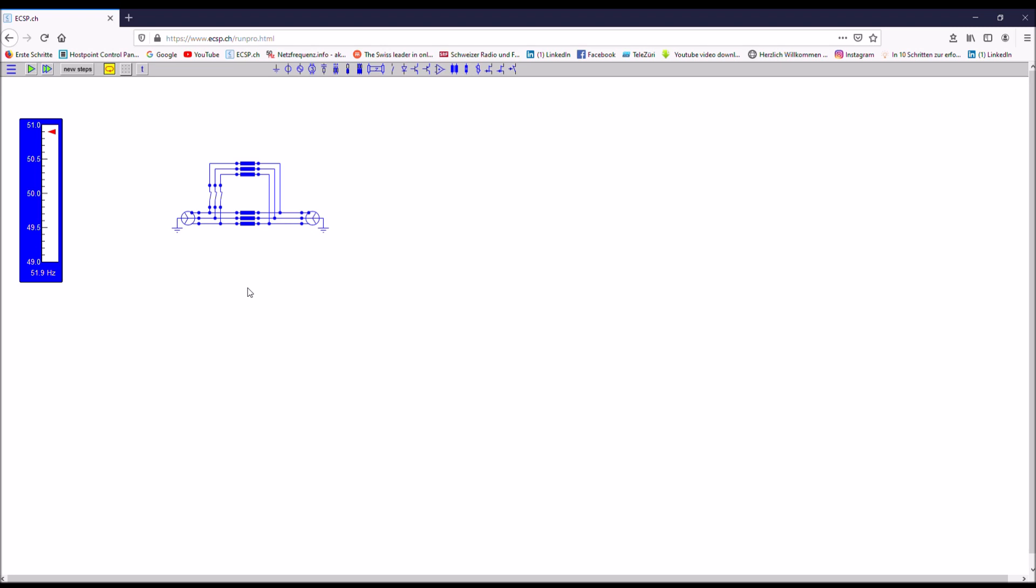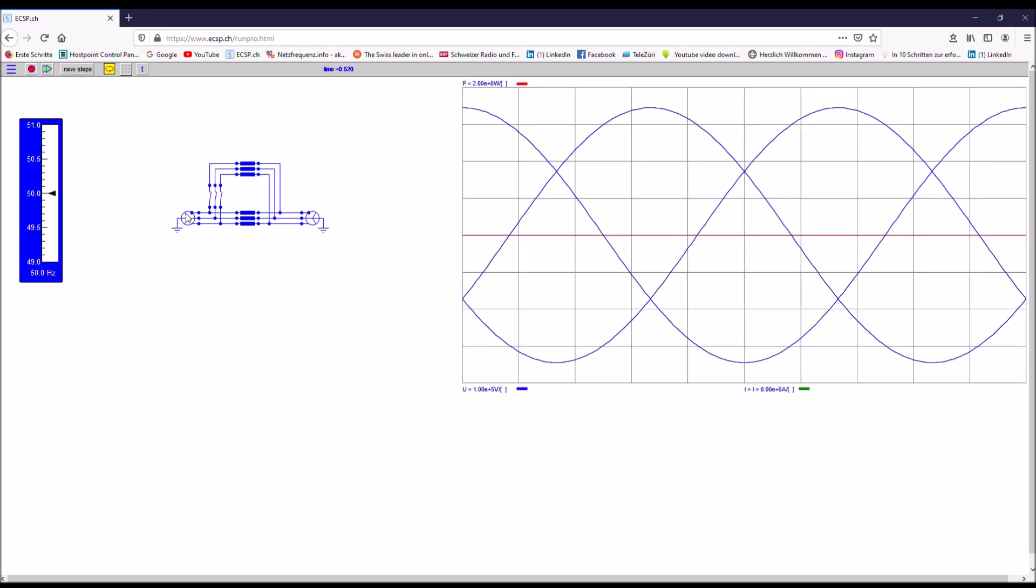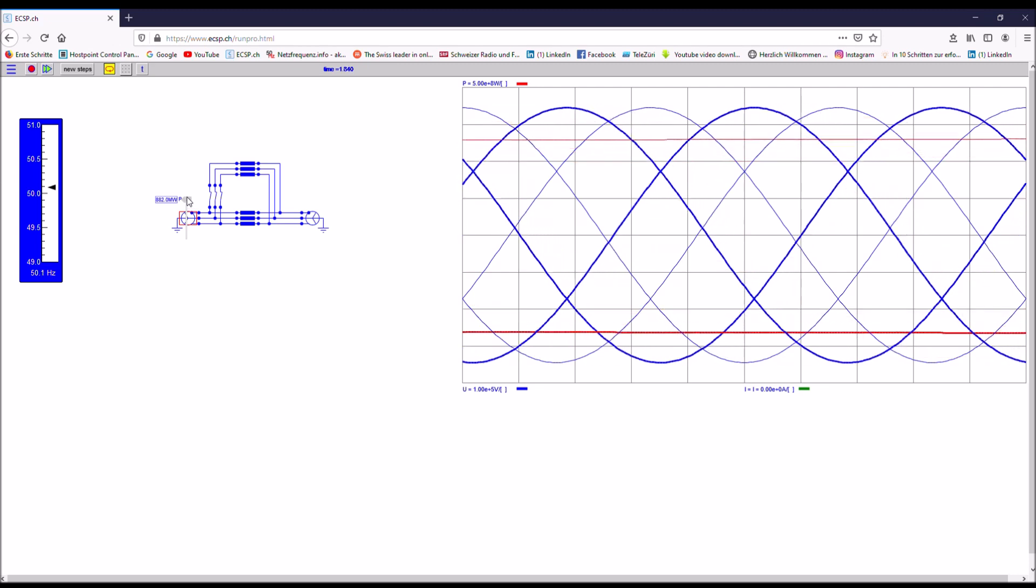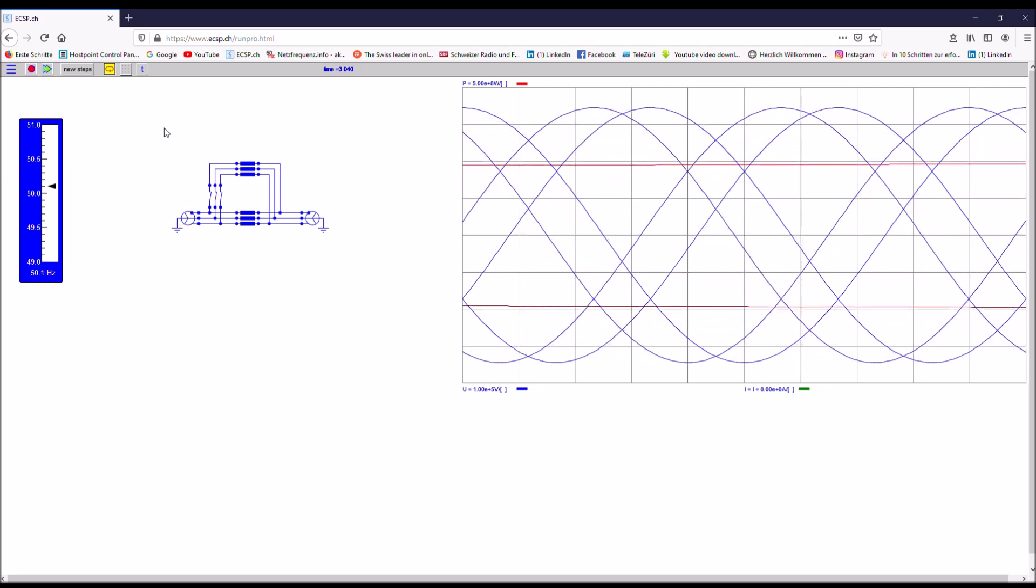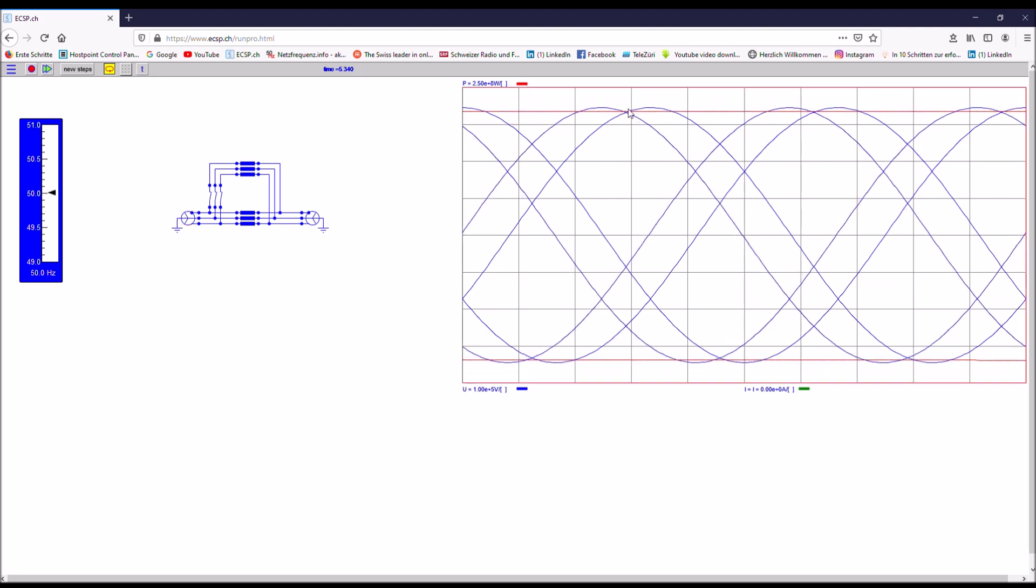Since I have now two parallel lines from one line end to the other line end, I can push double the power through the line system. And let's see what happens now if I lose one of the lines. So first I push the power to the maximum, and you can see that the phase angle between the line ends are still well below 90 degrees.